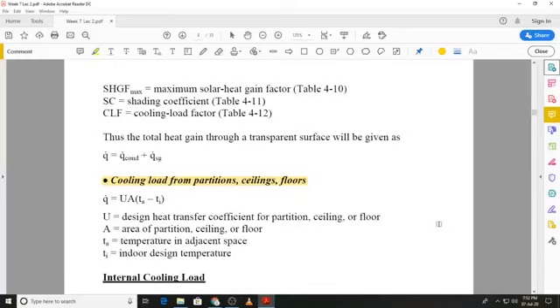The cooling load from partitions, ceilings or floors: I told you that ceilings and floors can also act as partitions depending on the construction. To calculate the rate of heat gain through partitions, again the standard heat transfer equation is used, that is Q is equal to UA delta T, and this time delta T is T A minus T i, where T A is the temperature in the adjacent space. It could be a room, it could be a basement, as I said, it could also be a room on the upper level. And we are assuming that because it's a heat gain, the temperature in the adjacent space is higher than the temperature inside the conditioned space.